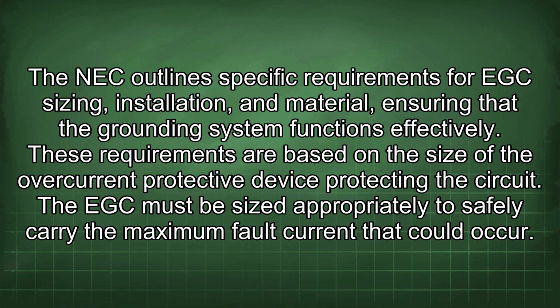The NEC outlines specific requirements for EGC sizing, installation, and material, ensuring that the grounding system functions effectively. These requirements are based on the size of the overcurrent protective device protecting the circuit. The EGC must be sized appropriately to safely carry the maximum fault current that could occur.